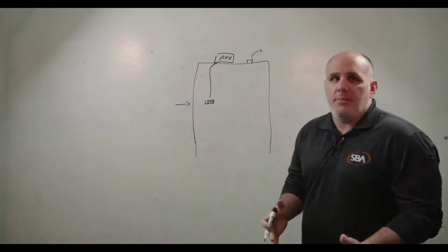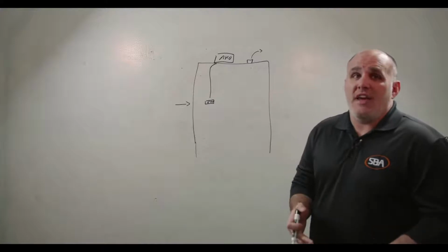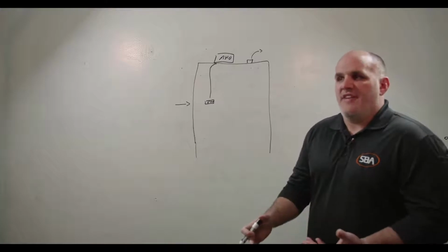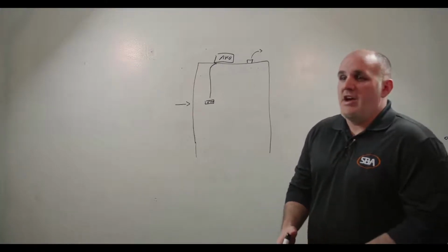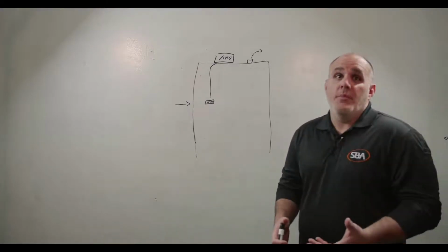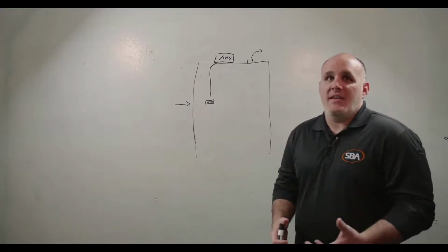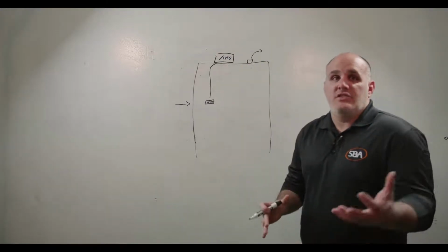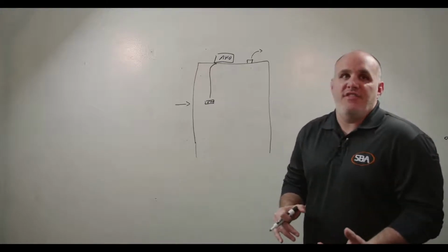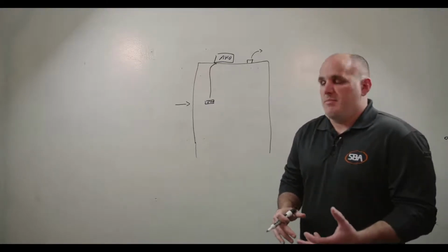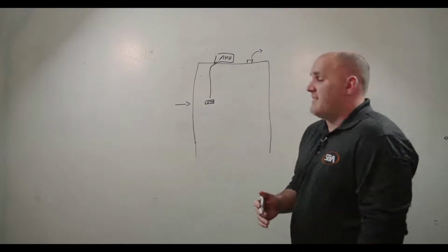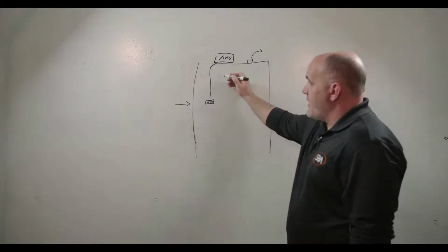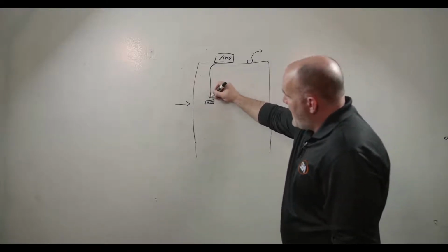I really like to delineate between the two because I used to do a lot of healthcare work, and it was really important you didn't call the exhaust fans relief fans and you didn't call the relief fans exhaust, because if you're exhausting like a COVID patient room or someone who has SARS or something like that, those are going to typically be 8 to 12 feet up. You're going to see the tall exhaust stacks and you don't want to breathe that air, versus general relief air is not such a big deal if you're exposed to that. So that's why I keep hammering that difference. But the air is exhausted out, right? So we have air supplied in and we have air that is exhausted out.